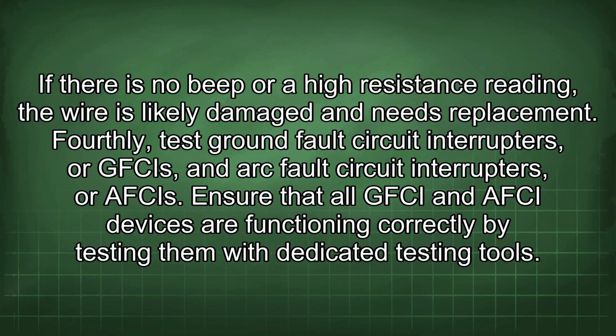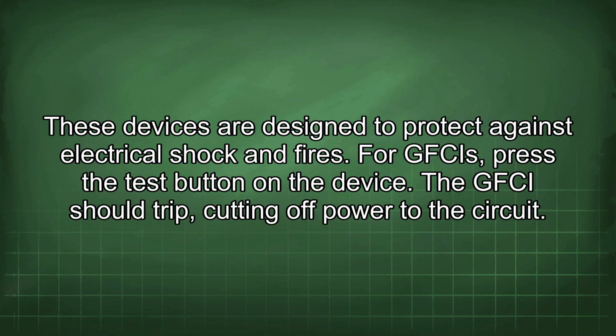Fourthly, test ground fault circuit interrupters, or GFCIs, and arc fault circuit interrupters, or AFCIs. Ensure that all GFCI and AFCI devices are functioning correctly by testing them with dedicated testing tools. These devices are designed to protect against electrical shock and fires.